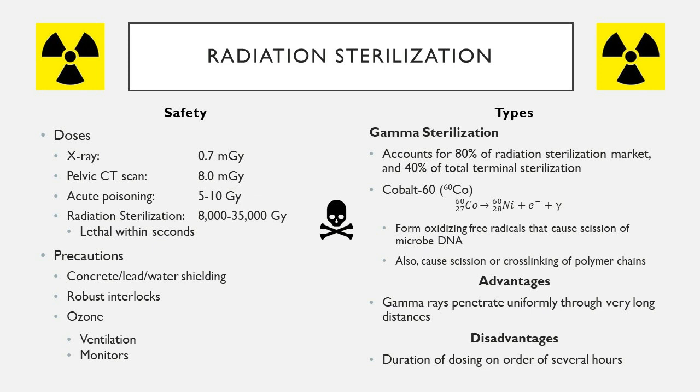Also, one thing I'd like to point out here is that while this source, cobalt-60, is itself radioactive, the gamma rays do not make the final product radioactive. So there's no radioactive components to the device once it comes off the sterilization process.